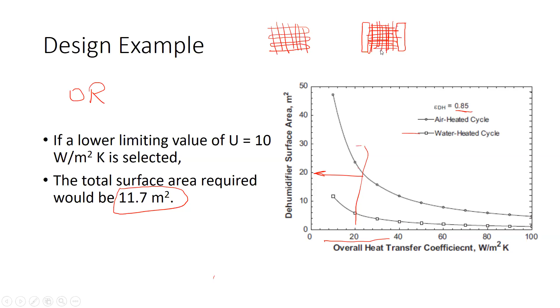What we normally do is go to the market, count the number of tubes, see the diameter of each tube, and calculate the total surface area. So you might find a unit in the market with 3 meters square. If the total area needed is 11, we need 4 units of this, and the 4 units are going to be placed as our heat exchanger or dehumidifier.